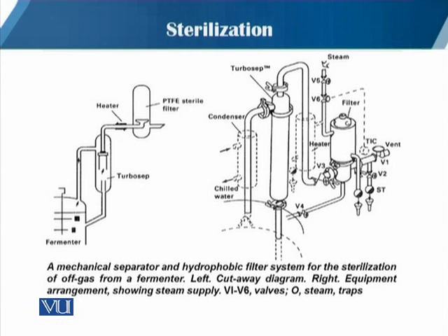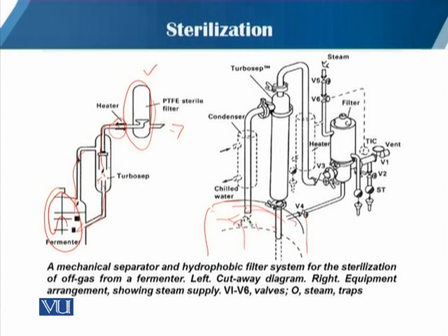In this slide, the first diagram shows the fermenter and the exhaust air path. Water condensation returns back to the fermenter, and the air passes through a heater and then through a PTFE filter to sterilize the air before it exits. In the second diagram, the exhaust air first passes through a condenser coil where water condenses and drops back into the fermentation vessel, then goes into a chamber, and again any condensation returns back.